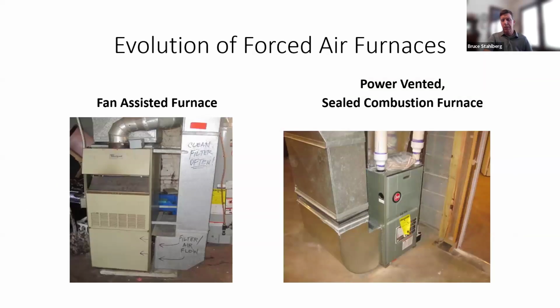And this is kind of where we've come with furnaces. On the left, we have either a natural draft or a fan-assisted furnace. These particular furnaces were pretty simple, just one heat exchanger, usually pretty large. Often back in the day, there was not a lot of air conditioning, so the air could easily move through the ductwork system. And then we come along and say, well, you can get more efficiency, so we install a high efficiency furnace. And these types of systems have a secondary heat exchanger. They require a lot more air. So that's a major change in the system.